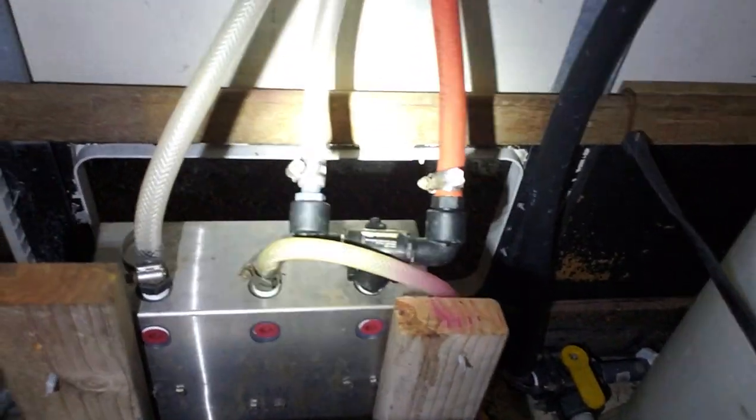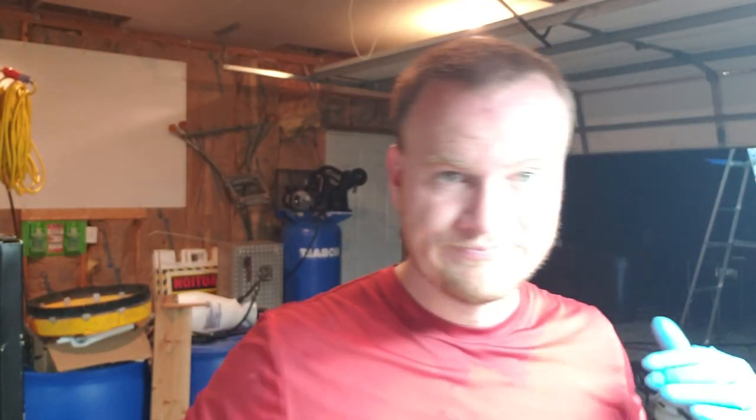Looks like we're good to go here. If you're getting air in your system, you're going to see water coming out most times, especially if you've got it sitting in there for a while. Make sure there weren't any other leaks all the way over. That connection looked good. Other than the top of it's got some leakage out there, which could even just be from my guys spilling stuff. After dealing with the other proportioner and air diaphragm pump and having to keep resetting it, seeing the air bubbles in there — let's go ahead and take the pickup tube and the bulkhead out.